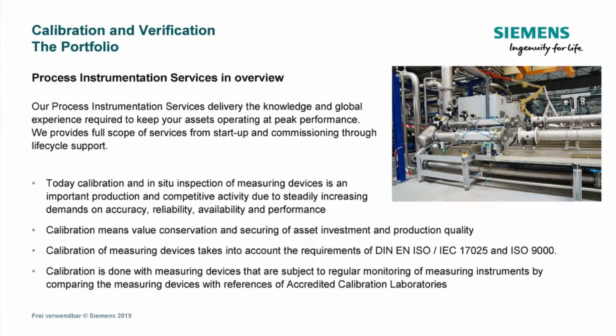Calibration means value, conservation, and securing of asset investment and production quality. Calibration of measuring devices takes into account the requirements of DIN, EN, ISO, IEC 17025 and ISO 9000. Calibration is done with measuring devices that are subject to regular monitoring of measuring instruments, by comparing the measuring devices with references of accredited calibration laboratories.